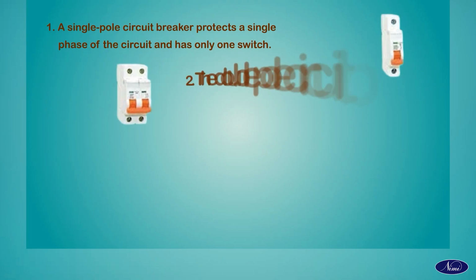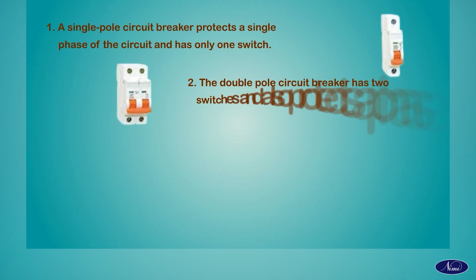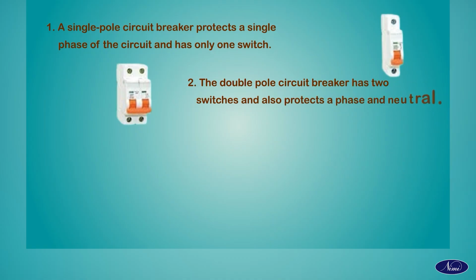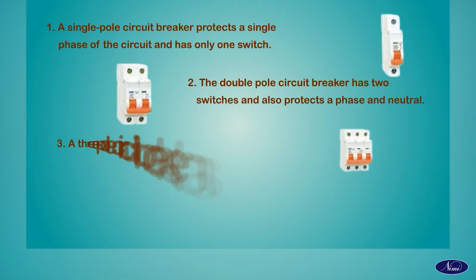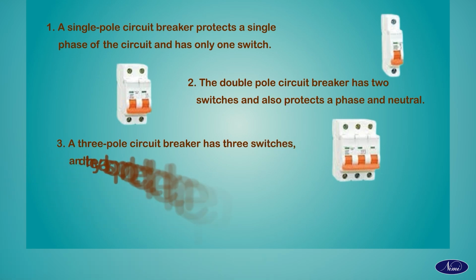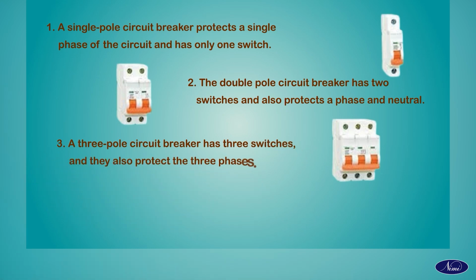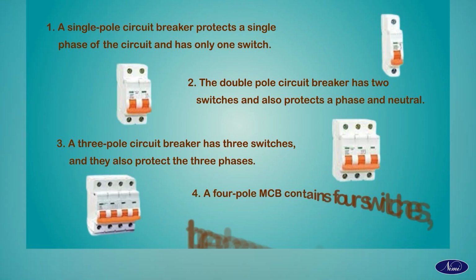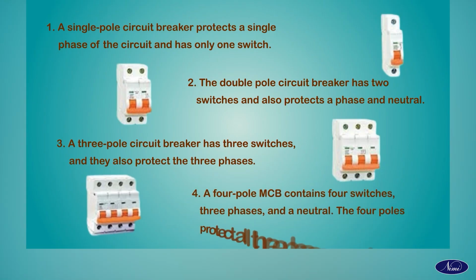A double pole circuit breaker has two switches and also protects a phase and neutral. A three-pole circuit breaker has three switches and they also protect the three phases. A four-pole MCB contains four switches, three phases and a neutral. The four poles protect all three phases and the neutral.